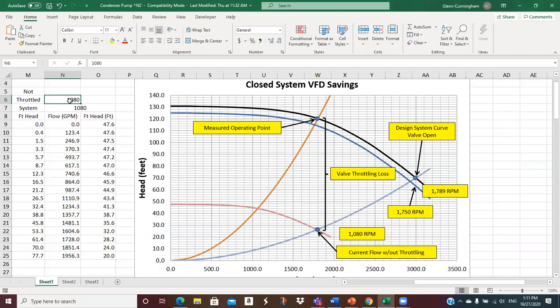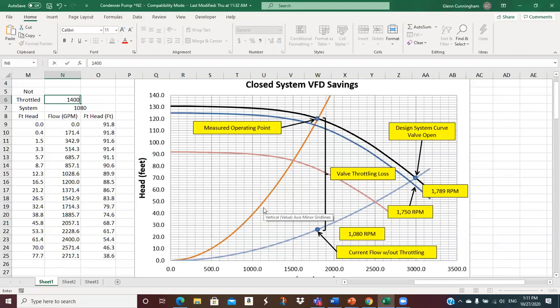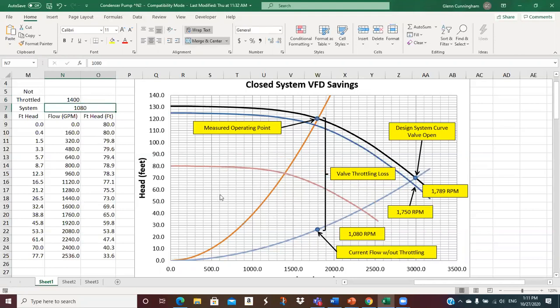You don't know exactly. I guess you could try to do a calculation, but if you get this program, let's say you start guessing speeds. So if I put in 1500, whoops, well, where'd my curve go? Well, see, this is this pump curve, but I can adjust the speed at which it operates, and the curve jumps. So you say 1500 now, because I'm not going through my desired operating point. So you can say, well, 1400. Well, it's getting closer. 1,200. I'm getting there. So anyway, you play around with it. 1080. Oh, ta-da! Goes right through my operating point.